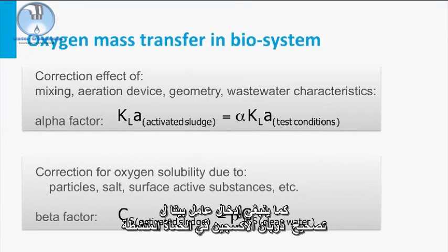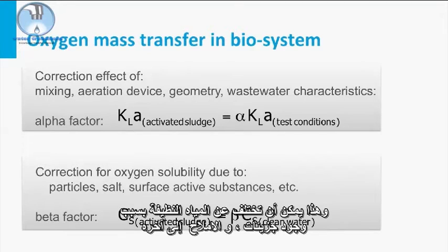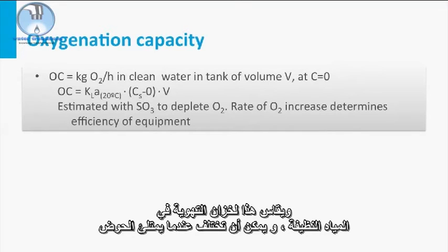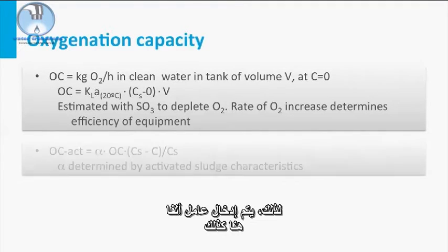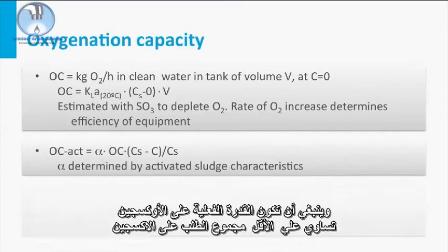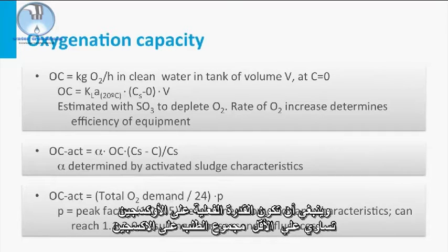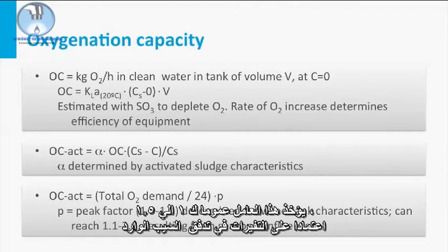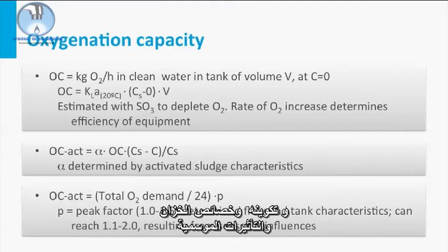A beta factor should also be introduced to correct for oxygen solubility in activated sludge, which can differ from clean water because of the presence of particles, salts, etc. The oxygenation capacity is measured in clean water and can differ when a tank is filled with activated sludge, so the alpha factor is introduced here as well. The actual oxygenation capacity should be at least equal to the total oxygen demand of the biological process times a peak factor, generally taken as 1 to 1.5 depending on fluctuations in influent compositions and flow, tank characteristics, and seasonal influences.